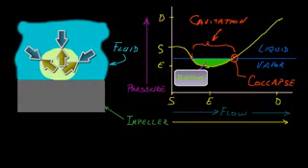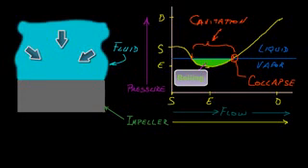During the process, the pressure of the fluid increases to the point that the gas bubble collapses rapidly under the increasing fluid pressure. This rapid collapse or implosion of the gas bubble is the cause of much of the damage that occurs during cavitation.